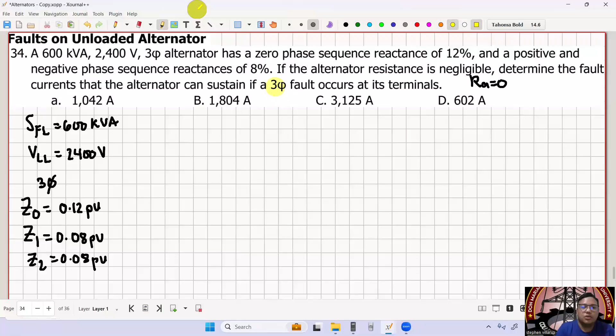Determine the fault current that the alternator can sustain if a three-phase fault occurs at its terminal. Take note, we want a three-phase fault here. Let's go back to our formula for a three-phase or symmetrical fault: fault current is equal to E per unit, the pre-fault voltage, over Z1, but this must be in per unit.